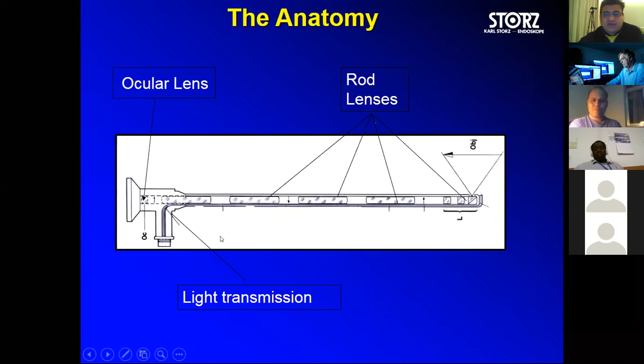There are two types of light cables which are used. One, the most popular, is a fiber optic light cable, and the other is a fluid light cable. Of course, the light transmission is very good in the fluid light cable, but the only risk is that if any sharp instrument pricks the fluid light cable, then the fluid is lost, and the life of the light cable is gone. So the preferred one is the fiber optic, which has hair-like fiber bundles. We'll see in a subsequent slide.